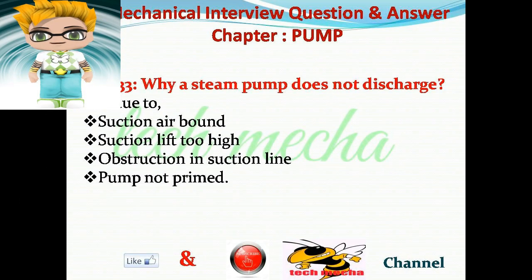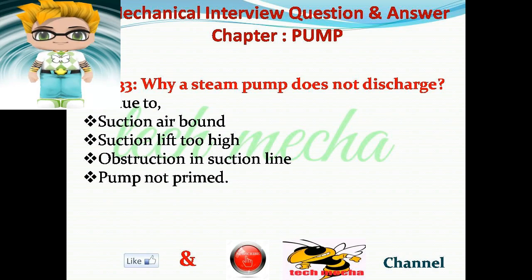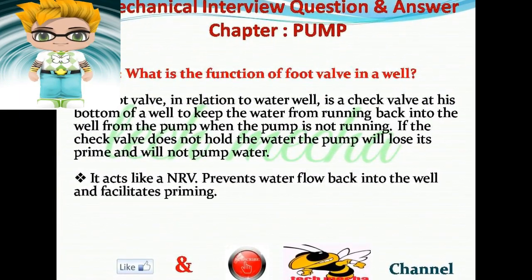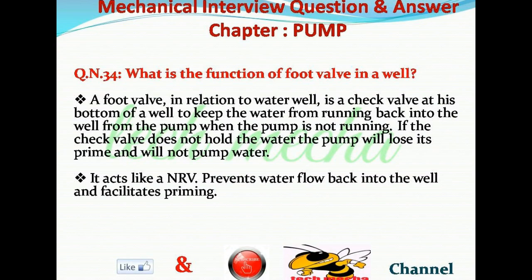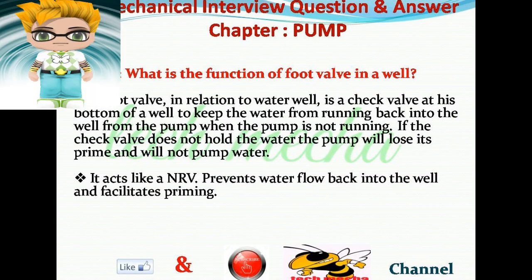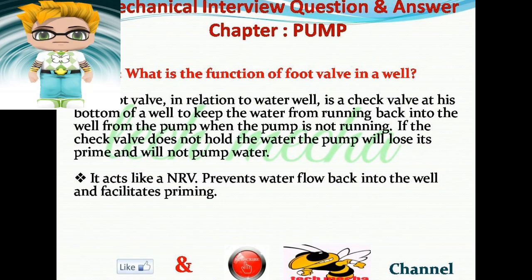Question number 33: Why does a steam pump not discharge? Answer: It is due to suction air bound, suction lift too high, obstruction in suction line, or pump not primed. Question number 34: What is the function of a foot valve in a well? Answer: A foot valve, in relation to a water well, is a check valve at the bottom of a well to keep water from running back into the well when the pump is not running. If the check valve does not hold water, the pump will lose its prime and will not pump water. It acts like an NRV, preventing water flow back into the well and facilitating priming.